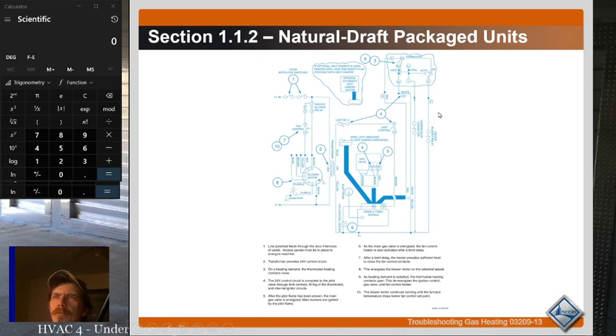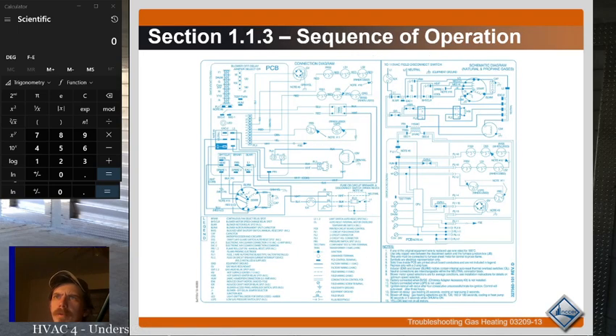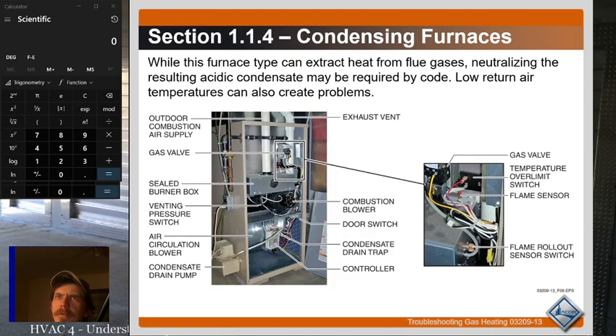It's a diagram for a natural draft package unit. Not super common. Most everything's going to be induced draft. Condensing furnaces. So a condensing furnace can extract the heat from the flue gases, neutralizing the resulting acidic condensate may be required by code. Low return air temperatures can also create problems. So a condensing furnace has two heat exchangers.